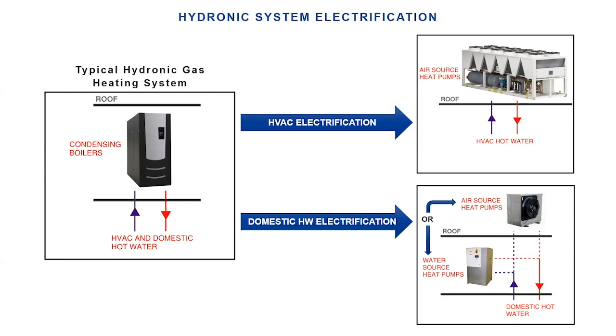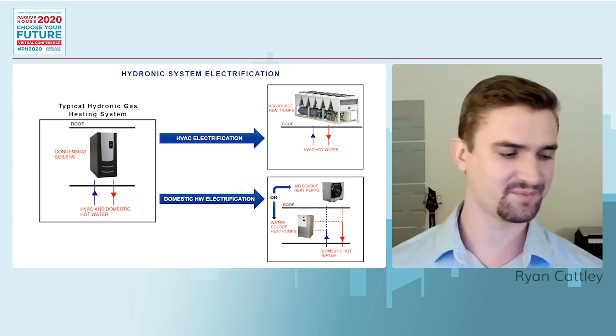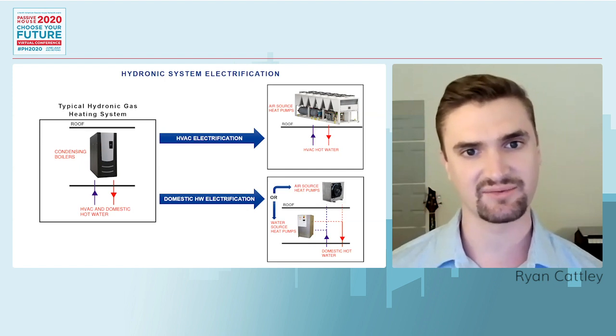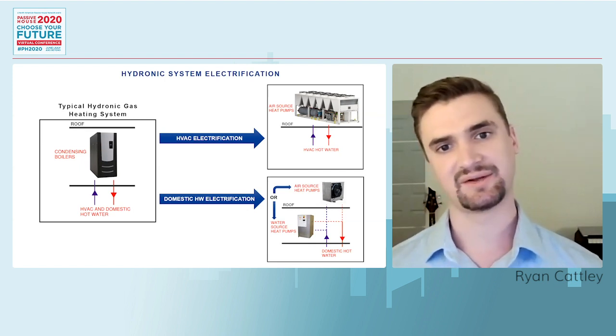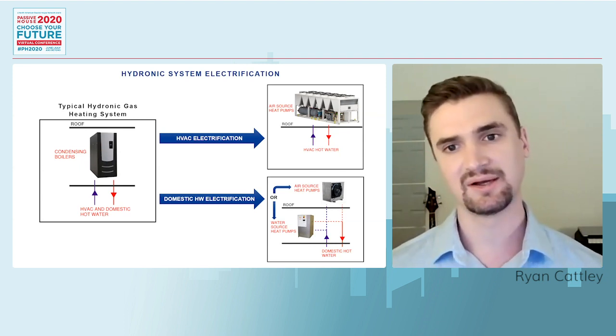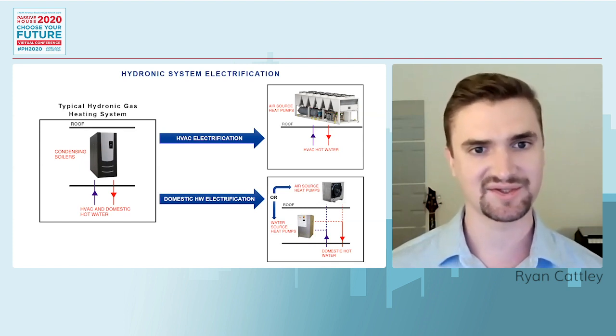Now there are some limitations with transitioning from a natural gas fired boiler plant to air or water source heat pumps for heating and domestic hot water. Air source heat pump space requirements can easily be on the order of 10 times the space required compared to a traditional gas-fired boiler plant. Air source heat pumps, at least with today's technology, cannot create as high a water temperature as a traditional gas boiler plant. Also, the day one utility costs, particularly in this region of New York City and New York State, will be much higher compared to gas, since natural gas is cheap per BTU compared to electric kilowatt hour costs.